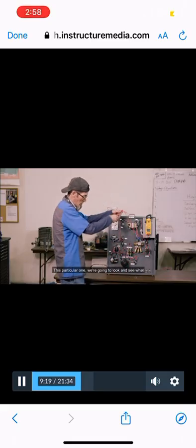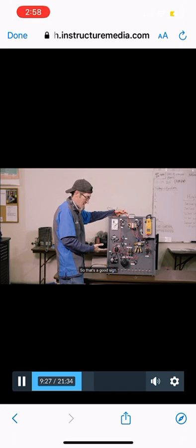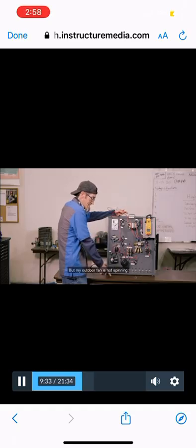Okay, this particular one, we're going to look and see what stops. Now, this one, a lot of students get pretty quickly. Sometimes they don't. You can see that the blower motor is still operating, so that's a good sign. My compressor light's still on. That's actually a good sign. That means that this thing is working correctly. But my outdoor fan is not spinning.